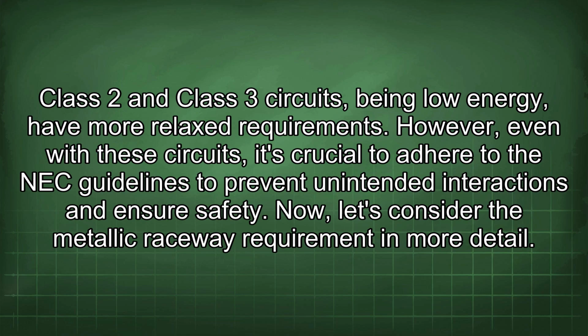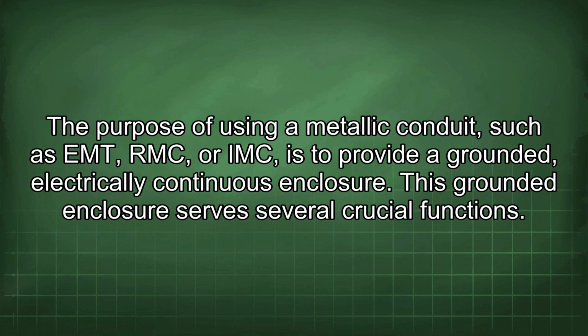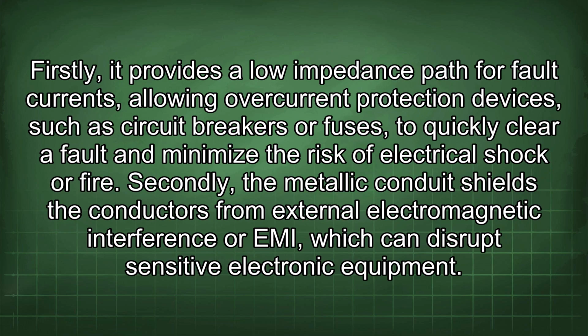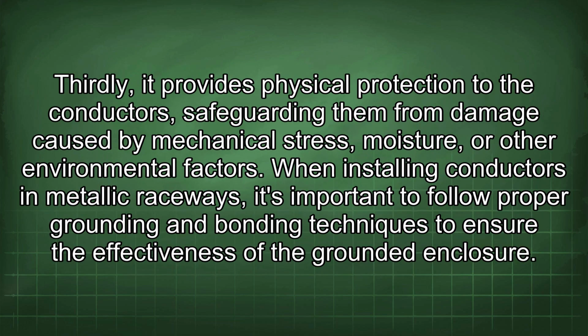Now let's consider the metallic raceway requirement in more detail. The purpose of using a metallic conduit such as EMT, RMC, or IMC is to provide a grounded, electrically continuous enclosure. This grounded enclosure serves several crucial functions. Firstly, it provides a low impedance path for fault currents, allowing overcurrent protection devices, such as circuit breakers or fuses, to quickly clear a fault to minimize the risk of electrical shock or fire. Secondly, the metallic conduit shields the conductors from external electromagnetic interference, or EMI, which can disrupt sensitive electronic equipment. Thirdly, it provides physical protection to the conductors, safeguarding them from damage caused by mechanical stress, moisture, or other environmental factors.